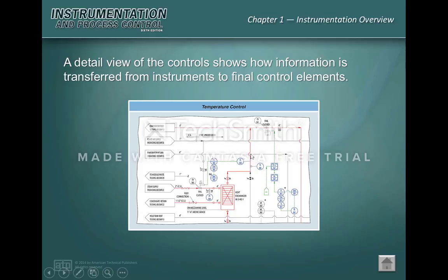You'll notice that it jumps over. It does not join. So we jump over and come up here to evaporated to DWG, fail closed valve. That must be our drain, our drain back. So we come up, we've got a valve here, we've got a valve here, we go through the heat exchanger. That's a 2-inch pipe, goes to a flexible coupling over to another valve, which is controlled. We have a TIC, temperature indicating controller. So here's a controller that's going to tell this valve yes or no to open based upon what's going on downstream.